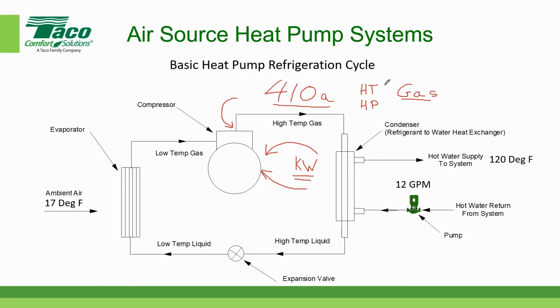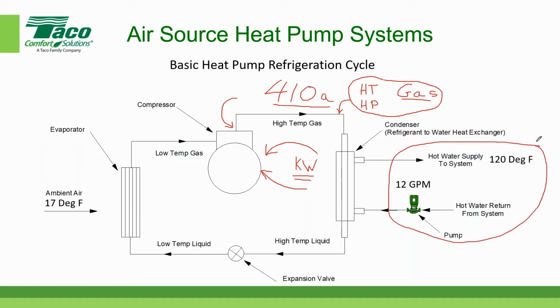So someone just asked a basic question here. This diagram is all internal to the actual unit, correct? They just wanted confirmation on that. Yes, pretty much, that's true. In terms of the modern air to water heat pump, all of these pieces, with the exception of, I'm going to kind of draw a bubble around this. This stuff is external, which is sometimes located physically inside the building, and all of this other stuff is outside the building and is contained in one enclosure.